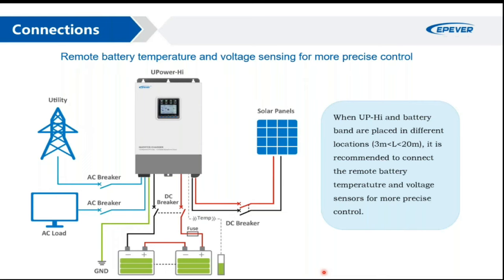And why would you need that? Because over long distances you will have voltage drops. So if your battery is far from your hybrid system, you will not be able to sense the voltage correctly. For example, if the voltage is 47, due to the voltage drops in the power lines, you would sense 46, and this will harm your batteries because you are never able to read the correct voltage. So the SOC will not be correct, and you will be in trouble.